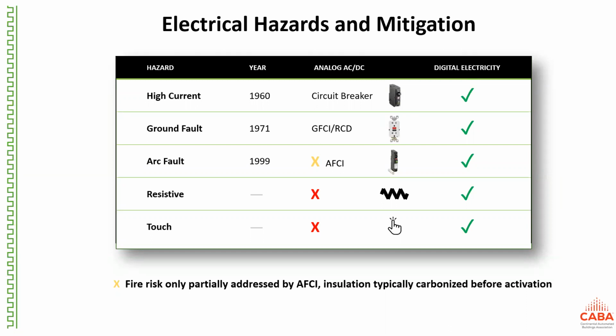When we go through that process of sending individual metered packets that are very small in energy content, it inherently covers all those faults. But very importantly, it covers two faults that aren't covered in the world today, which is a resistive fault, sometimes called a glowing fault, where on an AC receptacle someone doesn't tighten the screw down well, it turns into a heater and melts the receptacle down. It's actually the most common cause of fires in North America, and it's not covered by these other devices. It's not picked up, it's not really high current, so it's not picked up by a circuit breaker, it's not a ground fault, it's not an arc.